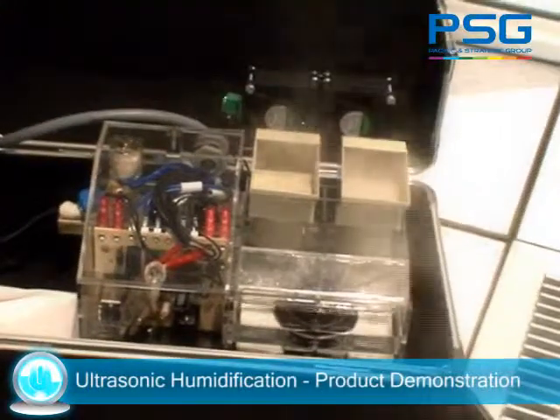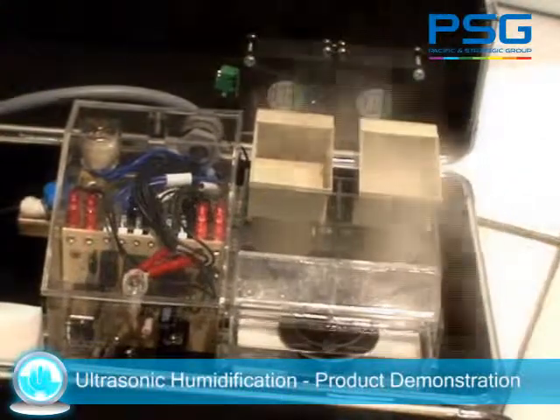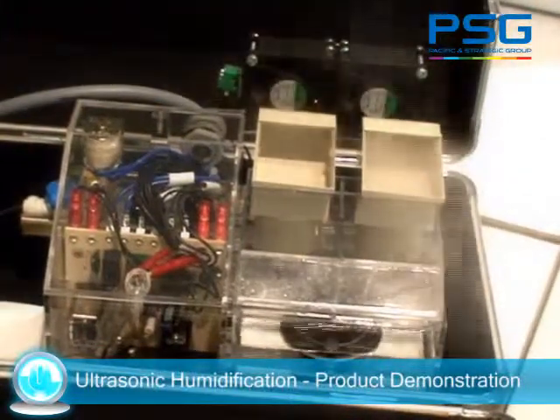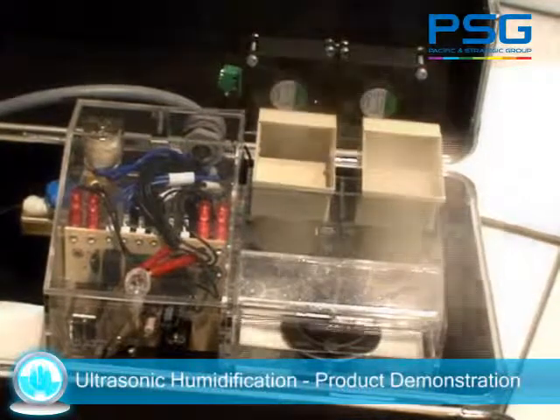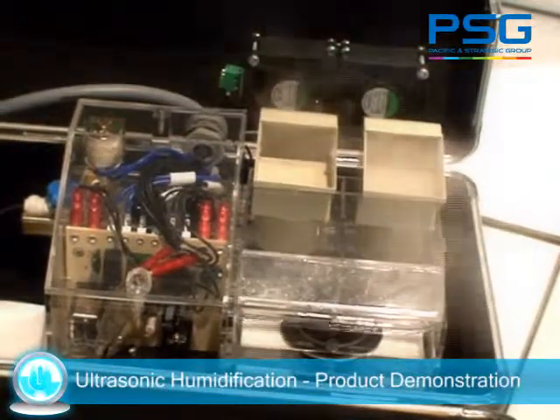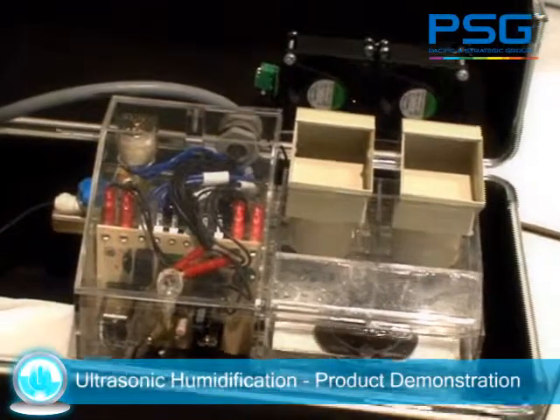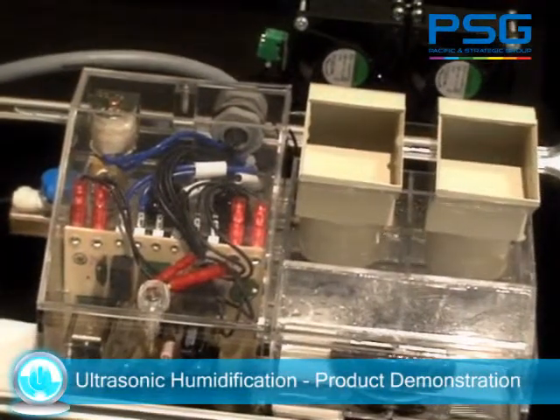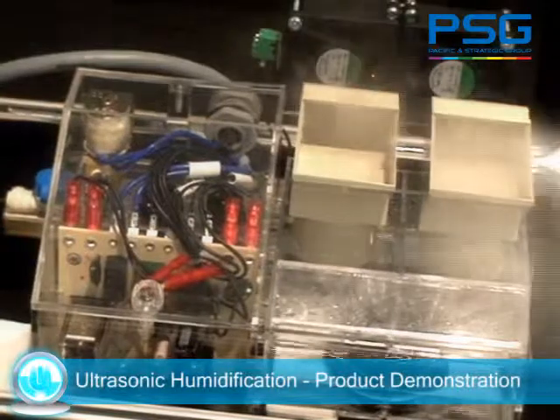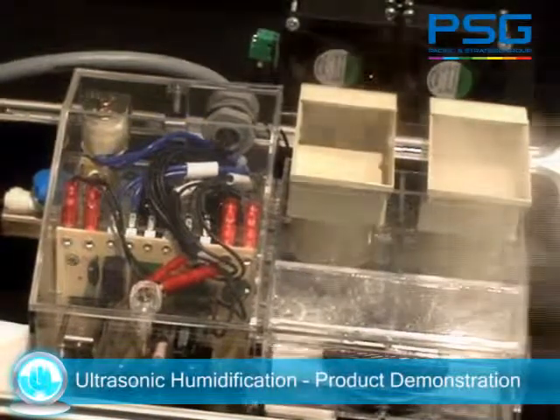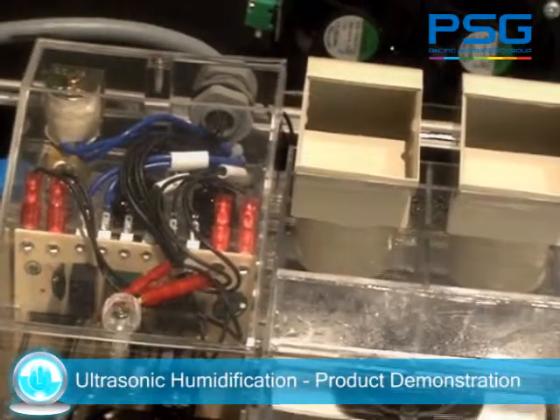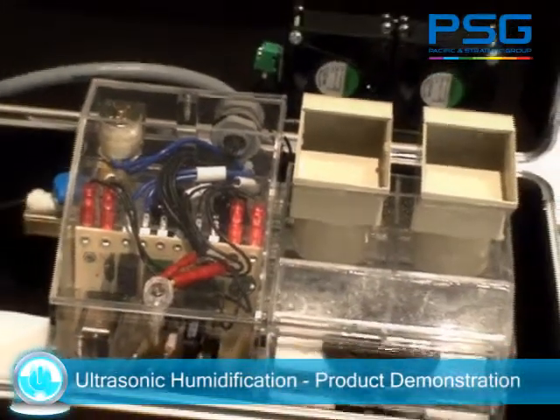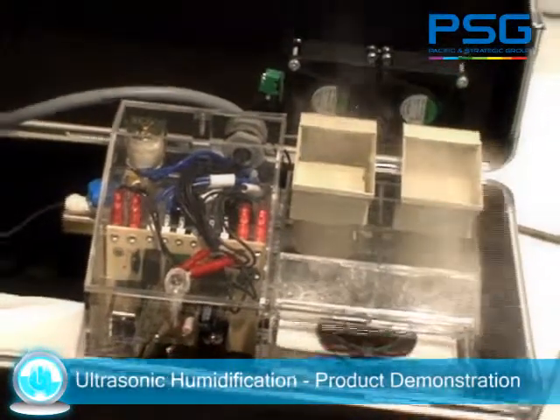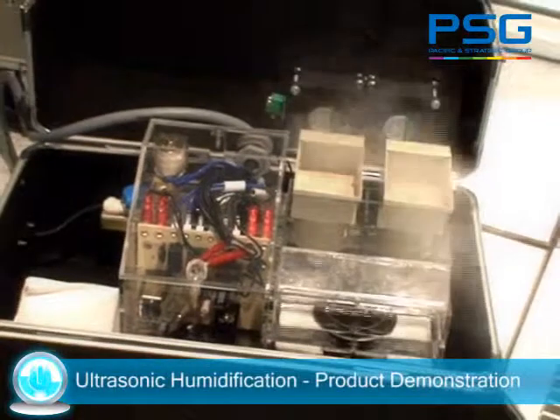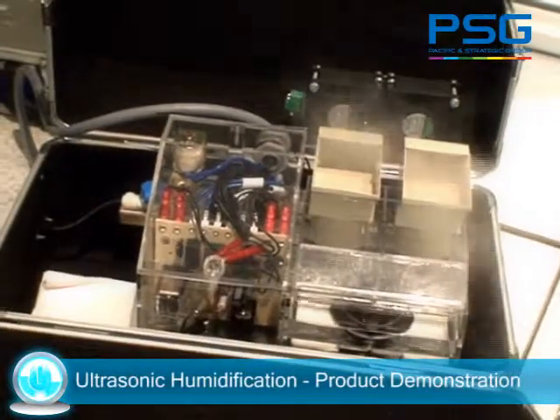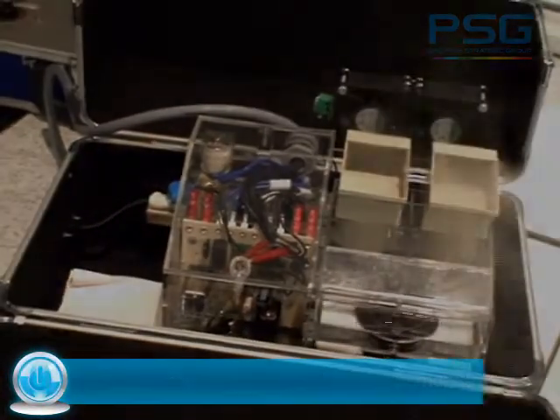The advantage is it's very low energy consumption, using only about 5% of the energy of a traditional immersed electrode system, and it's also very easy to control. It goes on and off instantly, and it also has part load characteristic controls. As you can see here, it's just operating on part load. It's getting near the set point, it's just going on and off. The transducers are being pulsed on or at full load.